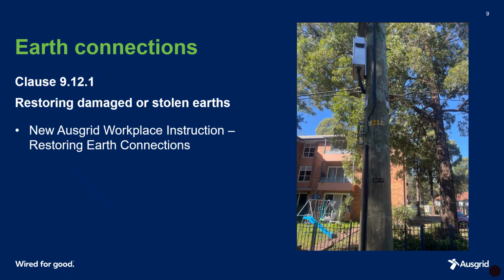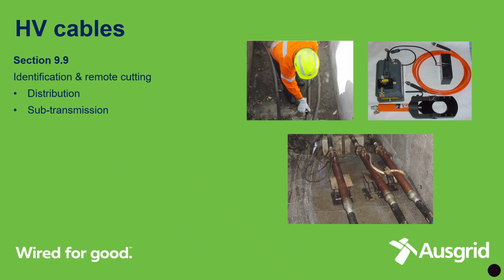Copper theft is a growing problem for the electrical industry, and Ausgrid is no exception, with the number of earth down leads being stolen increasing over recent years. To assist with the management of this situation, a new Ausgrid workplace instruction has been developed to allow electrically qualified Ausgrid workers to safely restore the earth connection to a surge diverter, with the surge diverter remaining energised. Clause 9.12.1 now includes an exemption to the need for an access permit to restore the earth connections to a surge diverter only where electrically qualified Ausgrid workers carry out the work in accordance with and implement the controls required by this new Ausgrid workplace instruction, restoring earth connections.